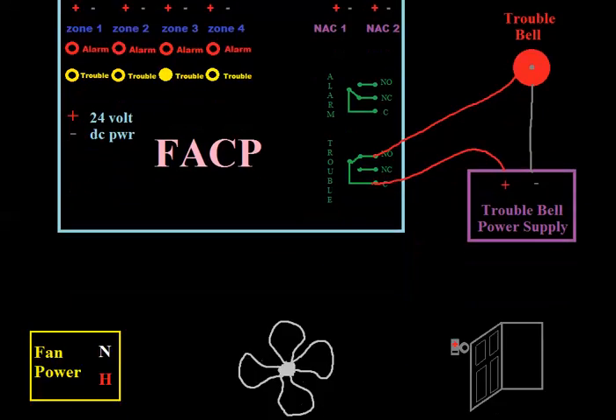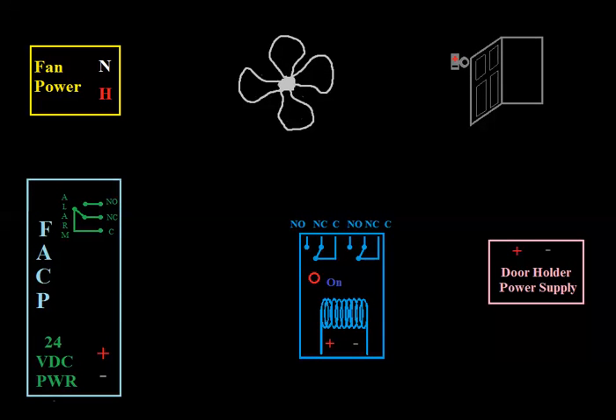I wanted to get a little deeper into relays. In the first video, using the school example again, we discussed what happens when the alarm goes off — fire doors close and the fans shut down. Let's say you had a pretty basic fire alarm panel with only one alarm relay. This is just kind of a snapshot of a panel. You can see there's some power here — 24-volt power. Most panels have non-resettable power, which always has a constant 24 volts, and resettable power, which loses power for about five seconds when you push the reset button. For right now, let's say this is 24 volts non-resettable power, so whatever I do, I'm going to have 24 volts right here.